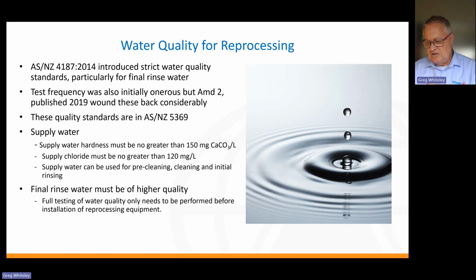Some of the microbiology needs to be done fairly regularly, but things like endotoxin testing have backed off substantially. Really, the water we're worried about for reprocessing medical devices is the final rinse water. You've cleaned the devices and got rid of the biological material, but the last thing you want is to rinse off all the dirty stuff with water that's contaminated with gram-negative bacteria eking out endotoxin everywhere. That's not common in reality, but it does happen.